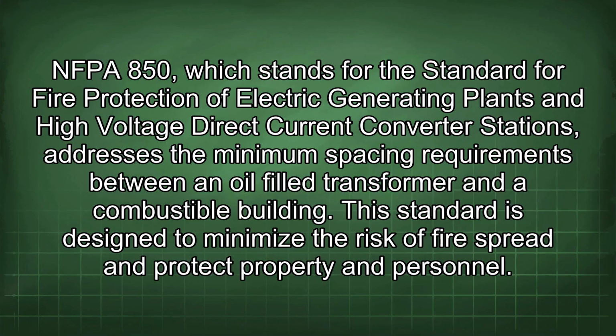NFPA 850, which stands for the Standard for Fire Protection of Electric Generating Plants and High Voltage Direct Current Converter Stations, addresses the minimum spacing requirements between an oil-filled transformer and a combustible building. This standard is designed to minimize the risk of fire spread and protect property and personnel.